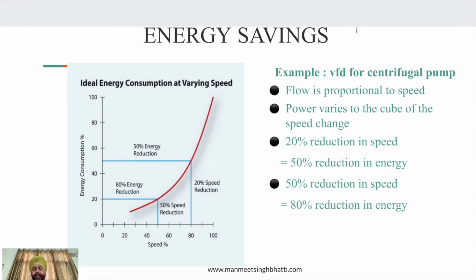Apart from that, reduction in the speed is also going to reduce your total load on the system, the pressure surges on the system, and any kind of leakages, because the pressure is very low. Now, if you further reduce the speed to around 50%, automatically, exponentially, your energy saving goes to around 80%. So this is a theoretical calculation.